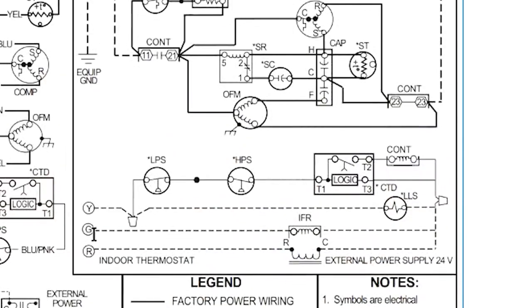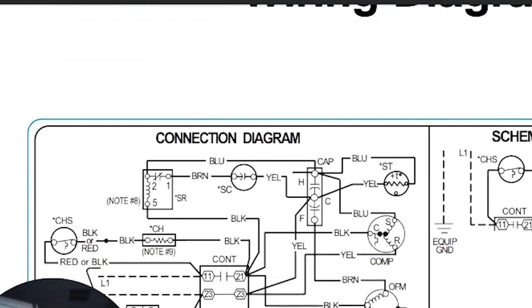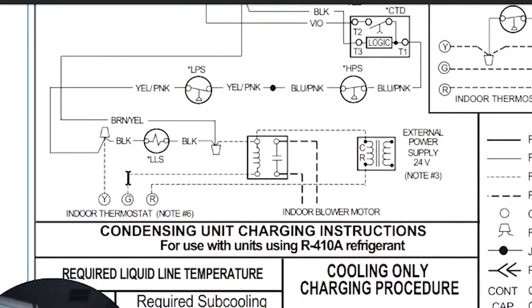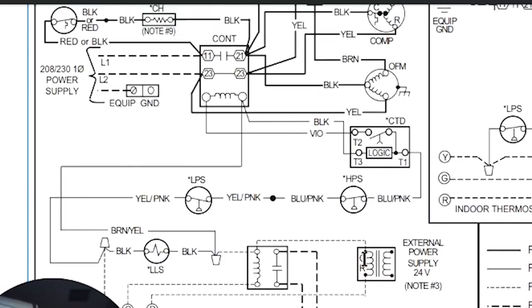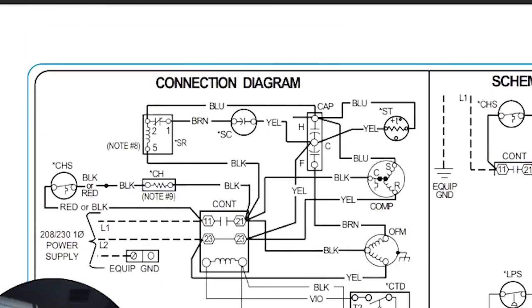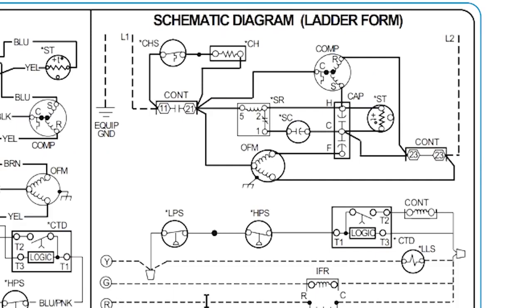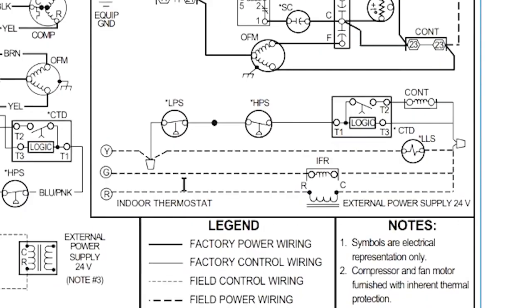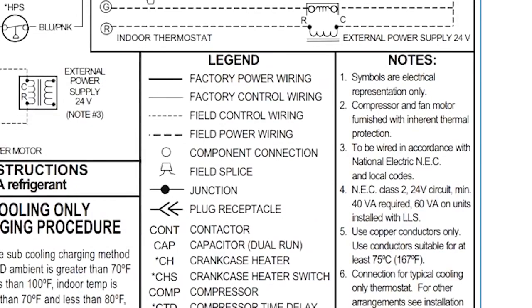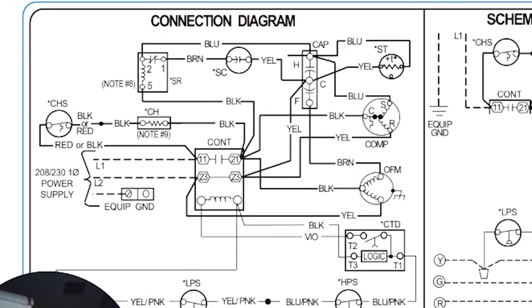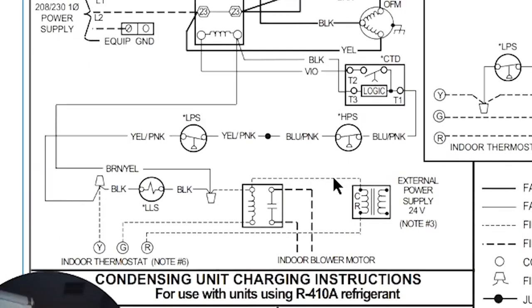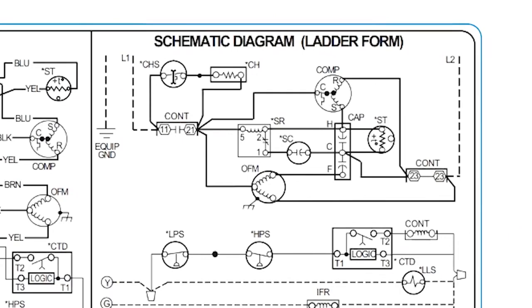An indoor fan relay is powered by G — that's all on the inside. Looking at the connection diagram: G powers a magnetic coil, which energizes a contact that brings on the indoor blower motor. The blower side isn't shown here because this diagram is only for the outside unit. We have the external power supply — the transformer inside — providing R, connected on the inside. This is wired for a basic straight-cool thermostat; it's not a heat pump setup.